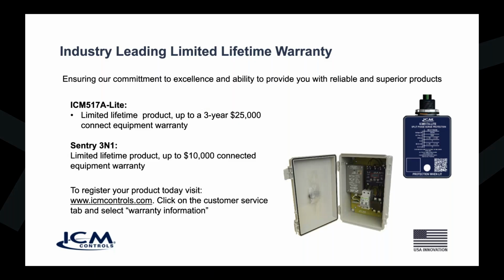All right, so maybe we can rehash what the surge protector does when we talk about lightning strikes and stuff. I hope I've made it clear that direct hits are not going to be protected against, because they're going to pretty much damage the equipment, split it in half, melt it. I mean, there are thousands and millions of volts behind a lightning strike, not even measurable in my mind. But lightning strikes cause surges to be transmitted down power lines and into equipment. And that's what the surge protectors are made to protect against, those fast-acting transient surges caused by lightning, but not the direct strike itself. For lightning strikes, you need lightning arresters and things like that, which are much different devices.